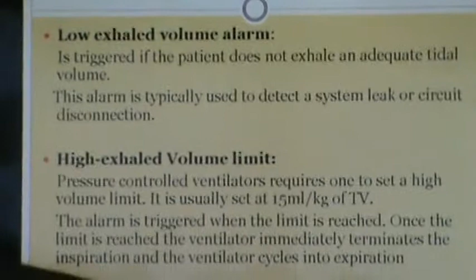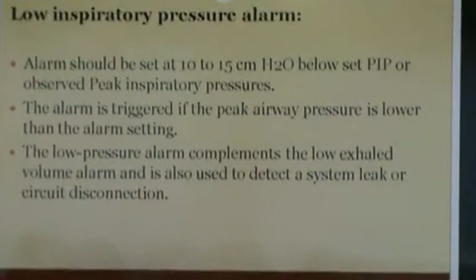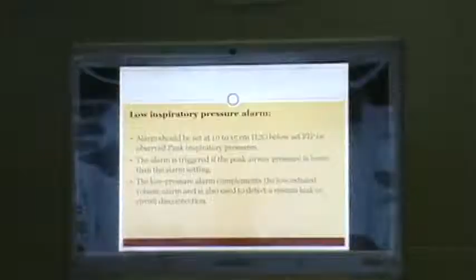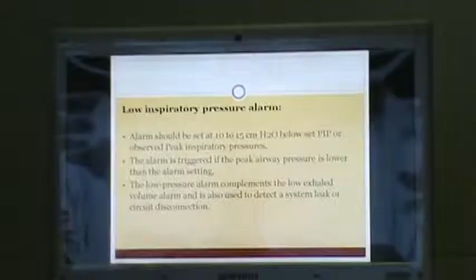Low inspiratory pressure alarm should be kept 10 to 15 centimeters of water below the set PIP. When this alarm is triggered, there is a fall in the pressure below the alarm setting. That will be the indicator that there is a leak in the circuit or a disconnection in the circuit.